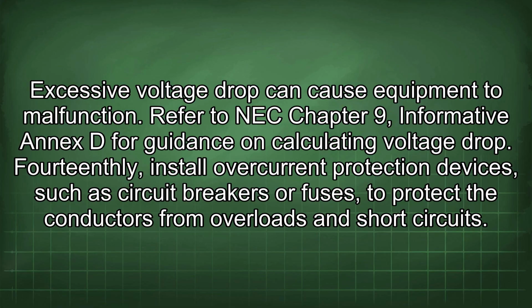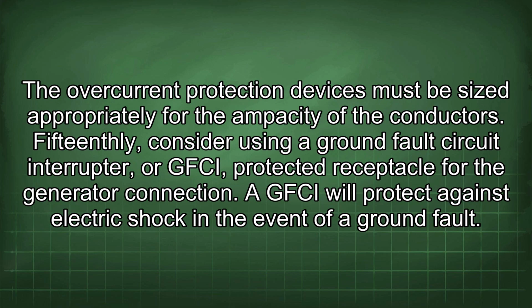14thly, install overcurrent protection devices, such as circuit breakers or fuses, to protect the conductors from overloads and short circuits. The overcurrent protection devices must be sized appropriately for the ampacity of the conductors. 15thly, consider using a ground fault circuit interrupter, or GFCI, protected receptacle for the generator connection. A GFCI will protect against electric shock in the event of a ground fault.